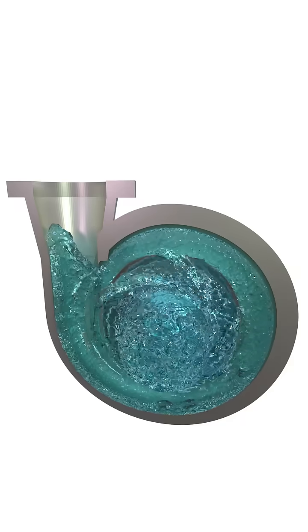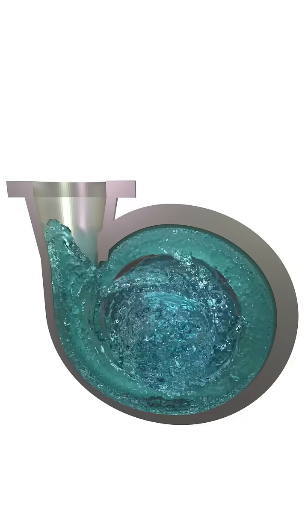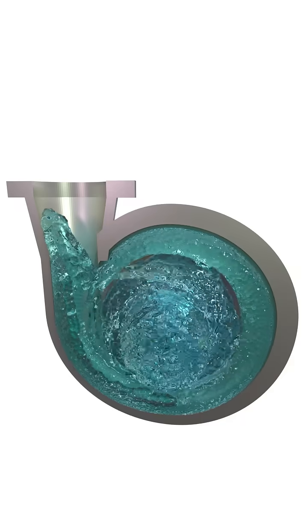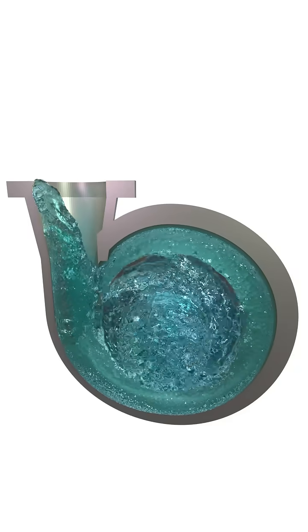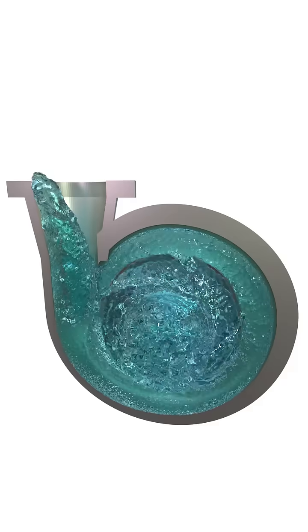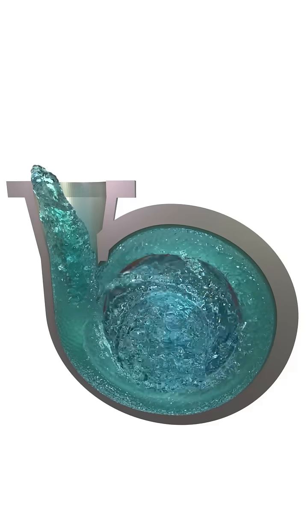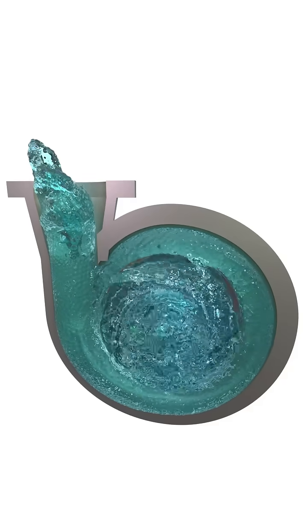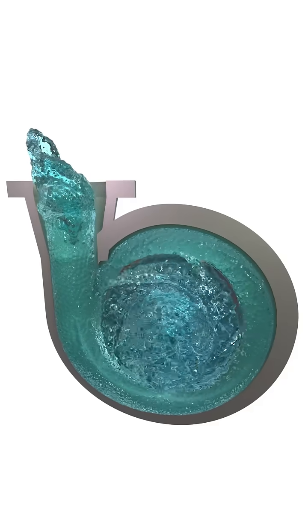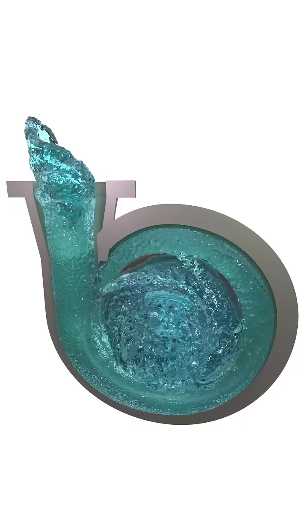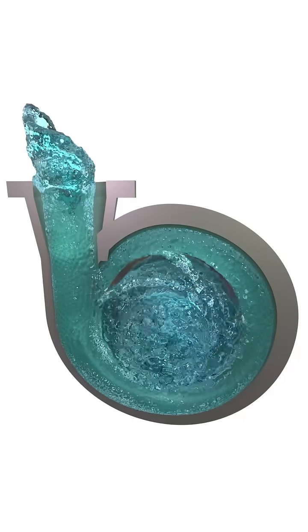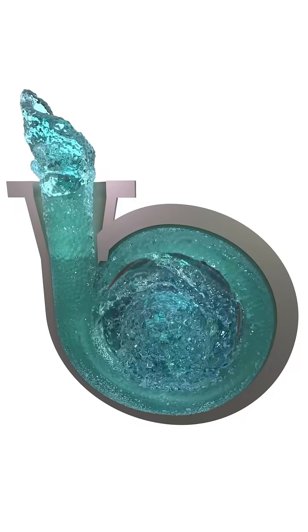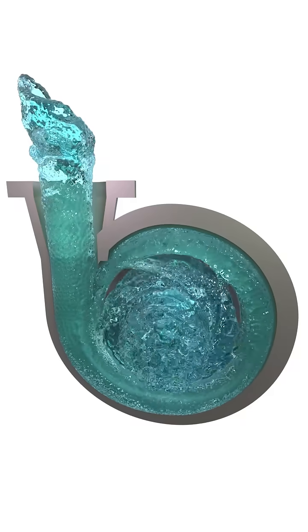They fall into the spiral casing to enter the diffuser connected to the pressure pipeline. The accelerated particles free up the central part of the pump and the pressure in this area decreases. Fluid from the suction pipeline rushes into the low pressure zone.